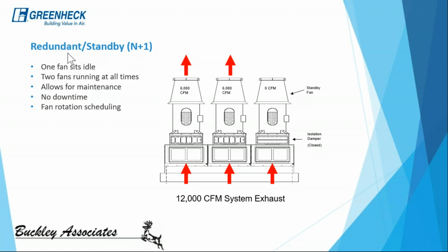What we have on this slide demonstrated is a 12,000 CFM exhaust system, where the one exhaust fan is in standby, and the other 2 fans are running at their design capacity of 6,000 CFM. They're basically splitting the load. And then naturally, based on different sequence of operations, we can work this out with you specifically. These fans can be rotated via scheduling to ensure equal runtime.